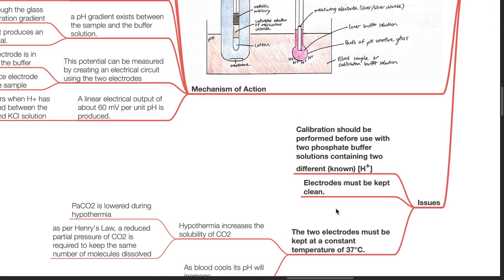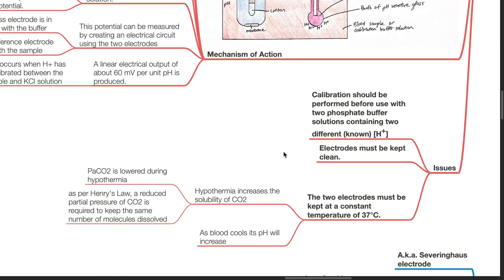Calibration should be performed before use with two phosphate buffer solutions containing two different known hydrogen ion concentrations. The electrodes must be kept clean. The two electrodes must be kept at a constant temperature of 37 degrees Celsius, as hypothermia increases the solubility of carbon dioxide. PaCO2 will be lowered during hypothermia and, as per Henry's law, a reduced partial pressure of carbon dioxide is required to keep the same number of molecules dissolved. As blood cools, its pH will increase.